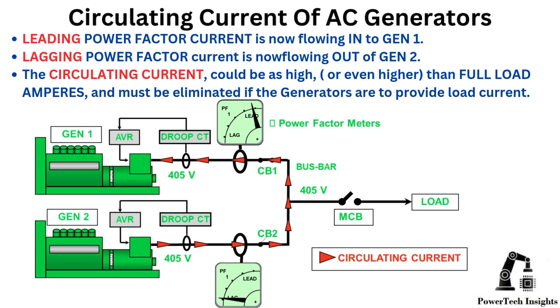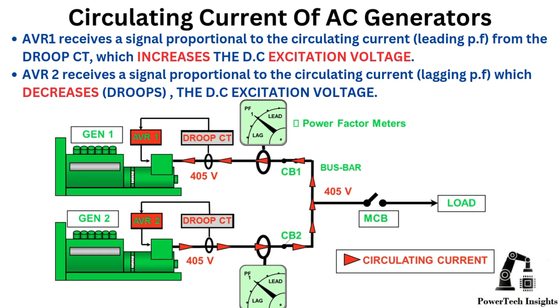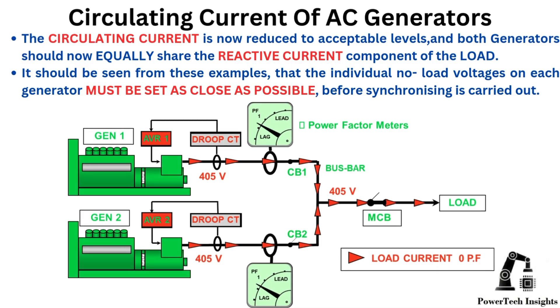Leading power factor current is now flowing into Gen 1; lagging power factor current is now flowing out of Gen 2. The circulating current could be as high or even higher than full-load amperes and must be eliminated if the generators are to provide load current. AVR-1 receives a signal proportional to the circulating current (leading power factor) from the droop CT, which increases the DC excitation voltage. AVR-2 receives a signal proportional to the circulating current (lagging power factor), which decreases (droops) the DC excitation voltage. The circulating current is now reduced to acceptable levels, and both generators should equally share the reactive current component of the load. The individual no-load voltages on each generator must be set as close as possible before synchronizing is carried out.